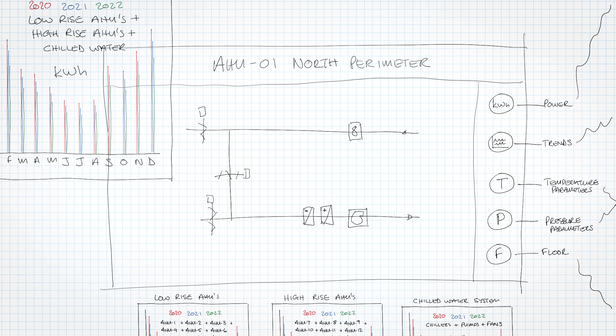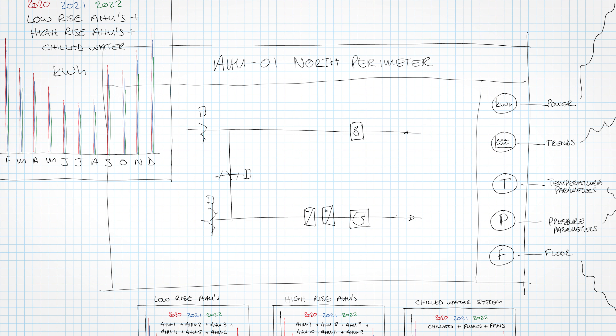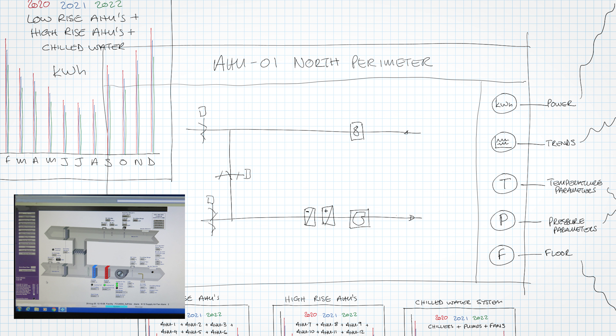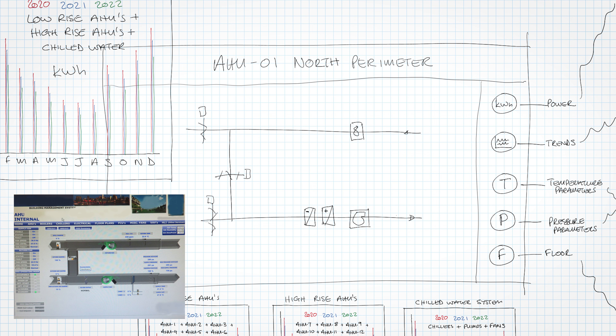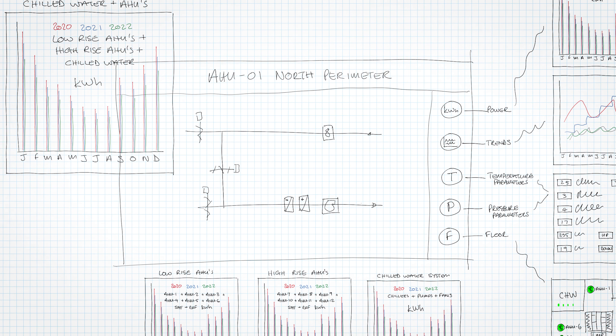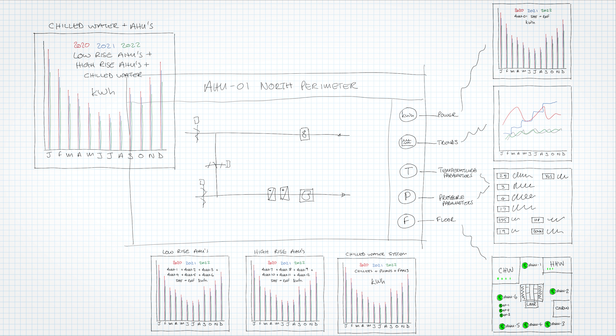Here we can see just a normal air handling unit, pretty much similar to what we discussed in the previous video - supply fan, return fan, heating and cooling coils, economy dampers. Our AHU graphics haven't changed much in the last 20 years. At the top there's the AHU 01 North Perimeter banner, which typically shows chilled water supply temperature, heating hot water supply temperature, and fire alarm status. What I really want to focus on is that right-hand side banner.